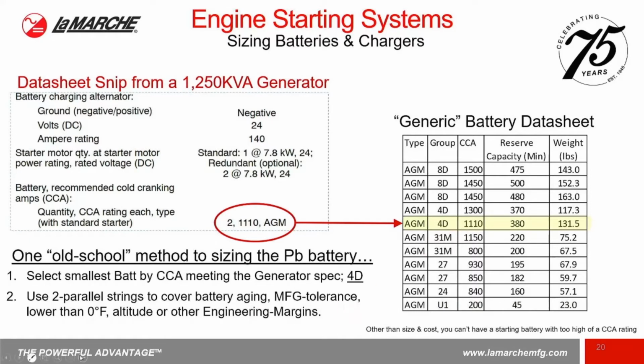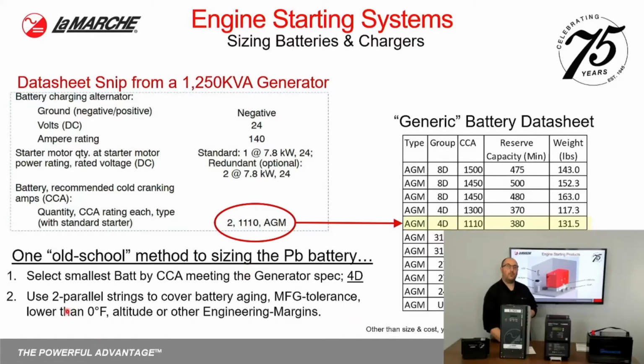After you've done step 1, you go to step 2 and say use 2 parallel strings. That gives you, it's not so much for redundancy, but it's there to help cover other terms like battery aging, the manufacturing tolerance from one battery to another, possibly operating lower than 0 degrees Fahrenheit, adjustments for altitude or other engineering margins. So this is really one of the reasons that you end up seeing 2 parallel strings.